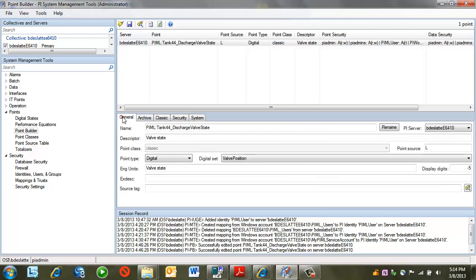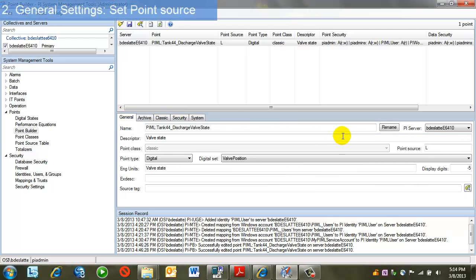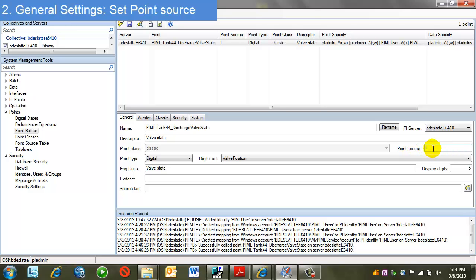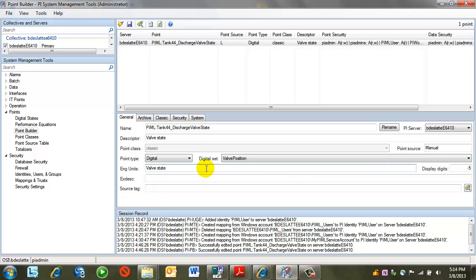Let's start with the general tab. The one parameter here of note is point source. By default, a new tag in PI gets a point source of L. I may want to assign a unique point source so that I can group all of my manual logger tags together. This will make things like tag searches easier to do. All the other parameters here are set just as any other tag in PI.